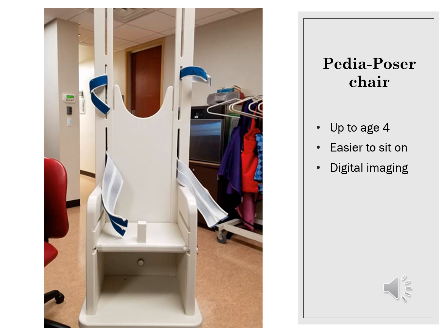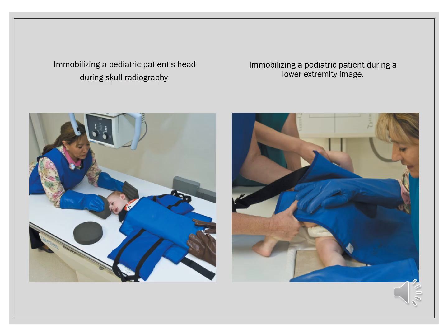The seat bench can be adjusted to accommodate infants up to toddlers aged 4 years old. The PediaPoser chair features a stable base equipped with wheel locks, ensuring it can be securely positioned after being moved to the desired location. With the rise of digital imaging, the use of the Pigg-O-Stat device has become less common. Many technologists now prefer to lay infants flat for recumbent radiographs, although this may not optimize lung expansion.